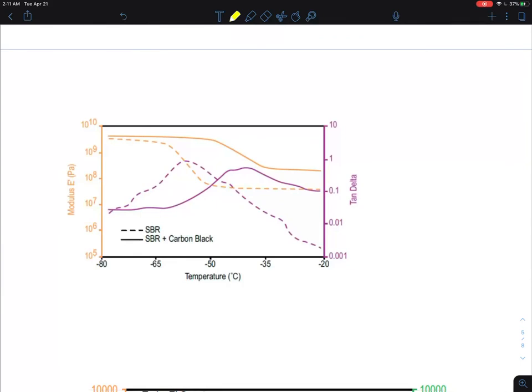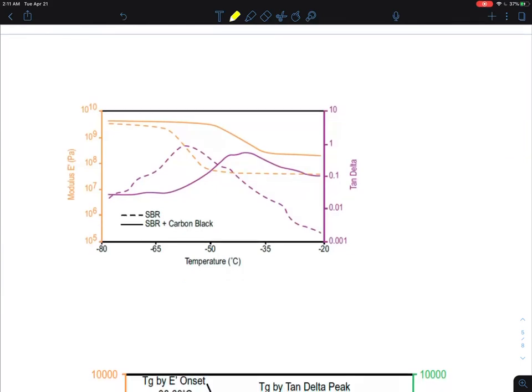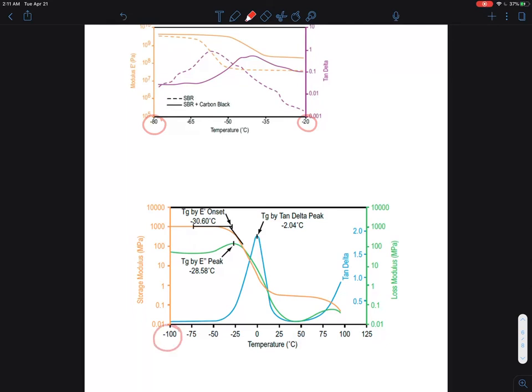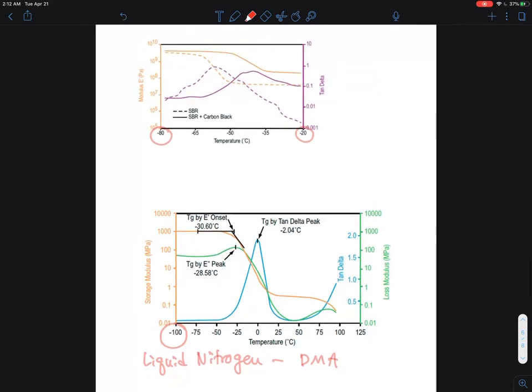Another example shows the temperature ranges — this is quite typical. DMA is very useful where DSC cannot give reliable measurements at colder temperature ranges. It is very common for DMA to have a liquid nitrogen cooling source, allowing temperatures much lower than room temperature. Here is an example going down to minus 100 degrees C, measuring Tg at low temperatures.